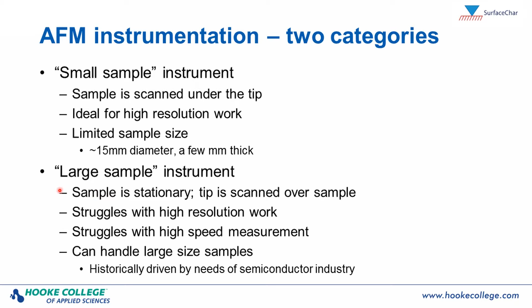The new system that has come out is a new entry into the large sample instrument category. Here is the new instrument that was released this year. It's called the Jupiter AFM by Asylum Research, which is an Oxford Instruments company. Here you can see a picture of the actual instrument. The instrument is in here, and you have some vibration isolation and the controller down here, so really it's a standalone instrument. Here are the pertinent specs of this new large sample instrument. In Z, it has a 12 micron range, which is quite large. A lot of instruments usually only go up to 5 microns.